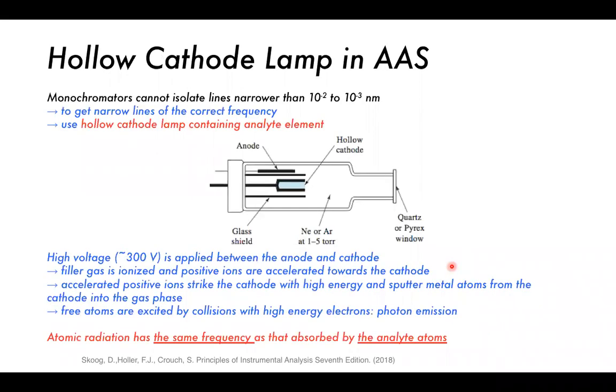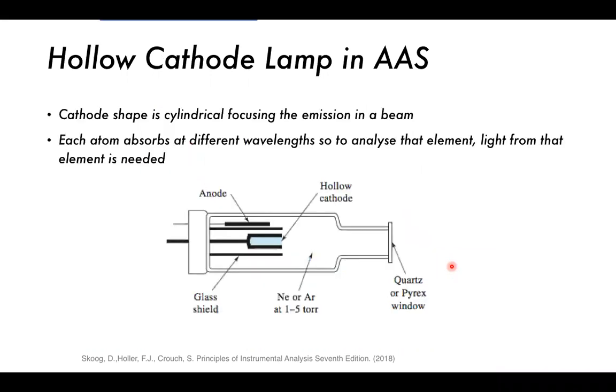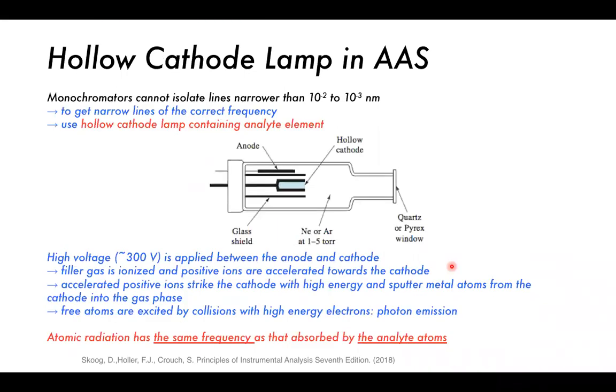In AAS, monochromators cannot isolate lines narrower than 10⁻² or 10⁻³ nanometers, which is why it's very necessary to get the correct frequency. To get narrow lines of the correct frequency, we need to use a hollow cathode lamp containing the analyte element, making the measurement really specific to our analyte.